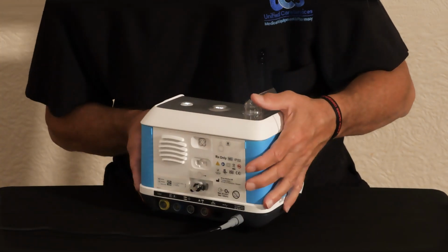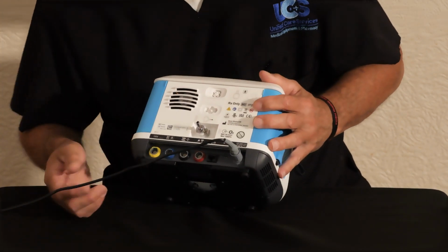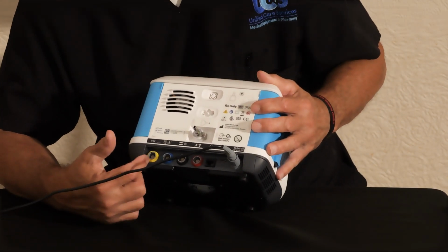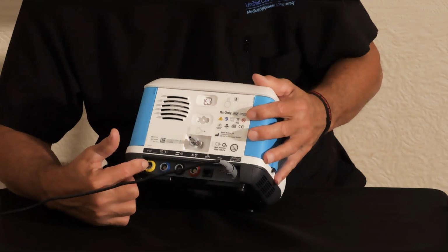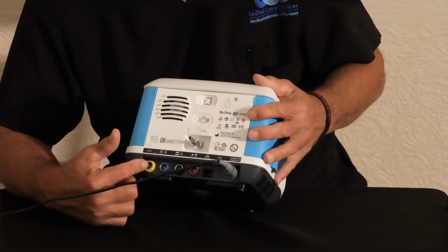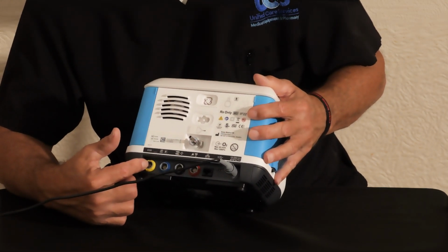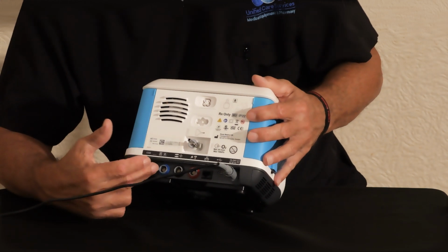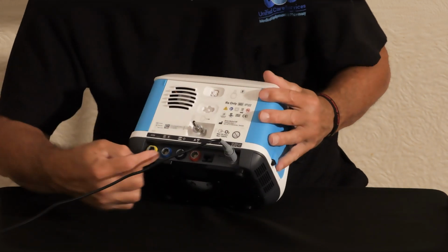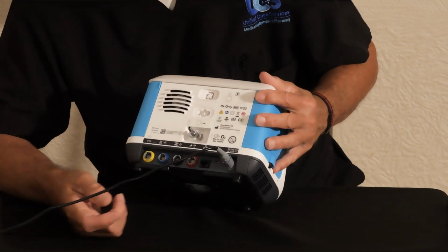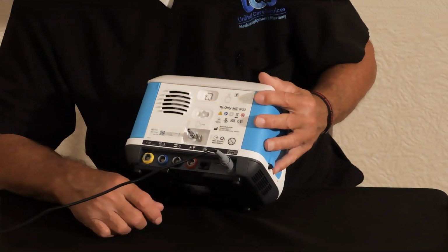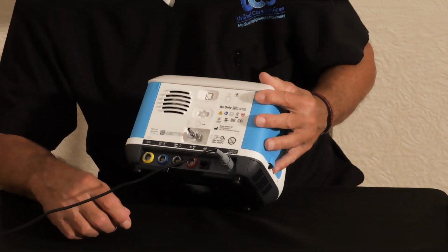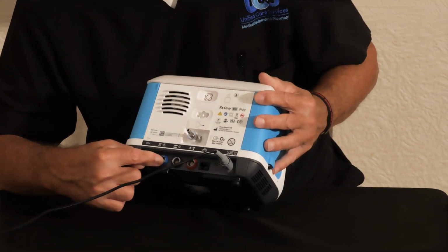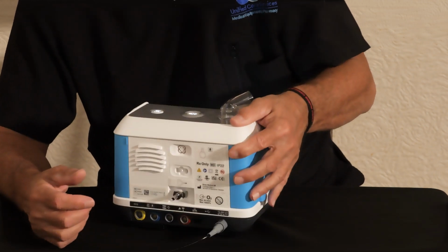Okay, also on the back of the ventilator here, you have where you can attach 2 cables. You have the yellow end-tidal CO2 cable that will connect to an adapter where you can actually measure the CO2. And on the back here, you have a blue cable that will measure the pulse oximetry on the patient. That cable connects directly to a probe to the patient's foot or finger.